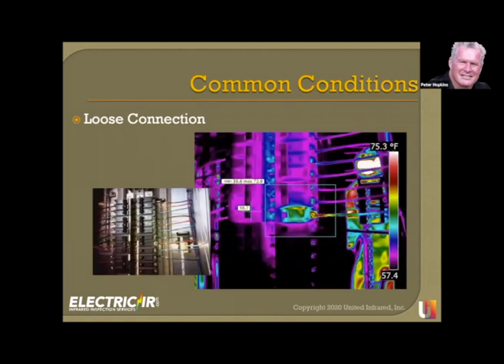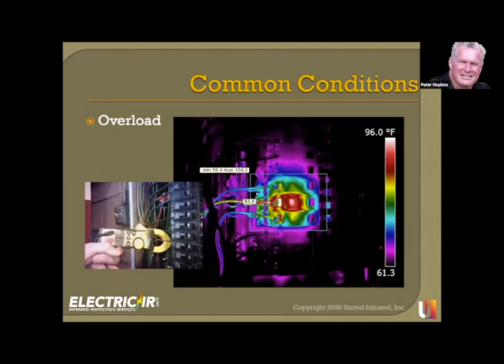This is an example of a loose connection and what you'll see thermography-wise. Keep in mind, with a loose connection the resistance is right at that point, so the wire gets cooler as it moves away. When you see a connection that's hot right at the screw, that tells you it's a loose connection indication. By the way, you can see my reflection in that image, it looks like I'm boiling, but what we're really seeing is a cold wire going hot, confirming a loose connection.